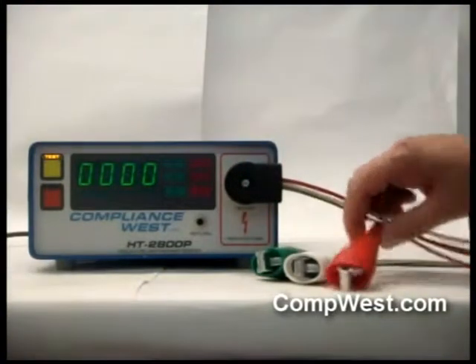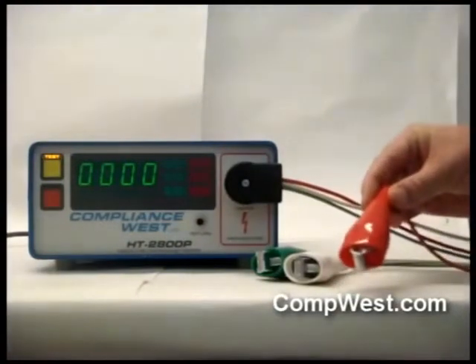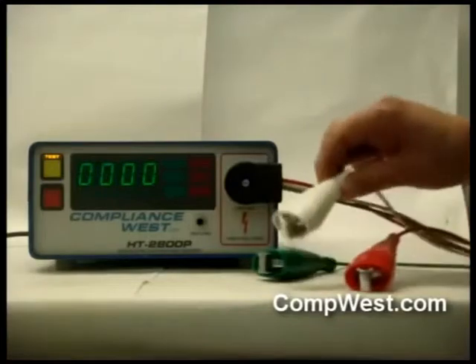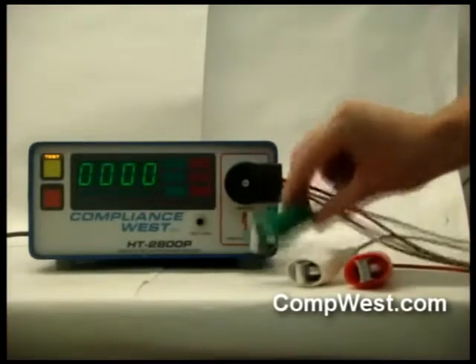Red connects to one hot. Connect a jumper to the other hot so they are connected together. White connects to the neutral bus. Green connects to the ground bus.